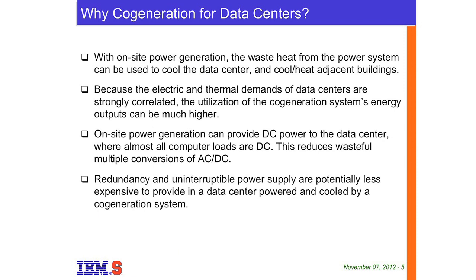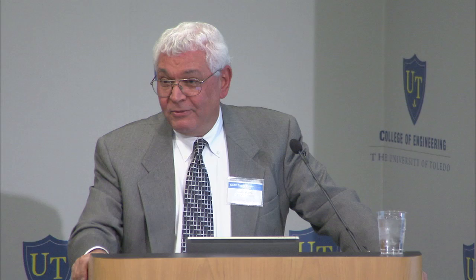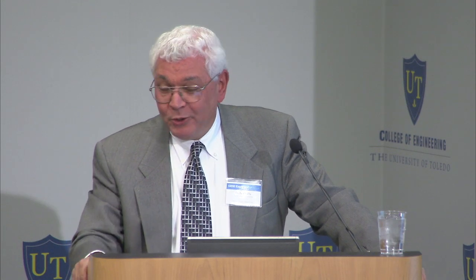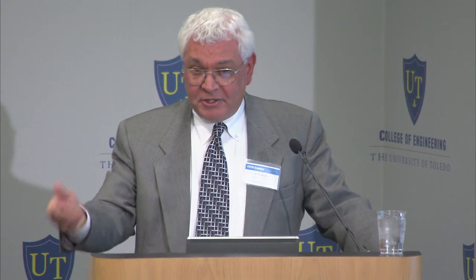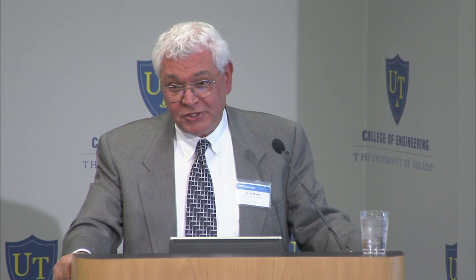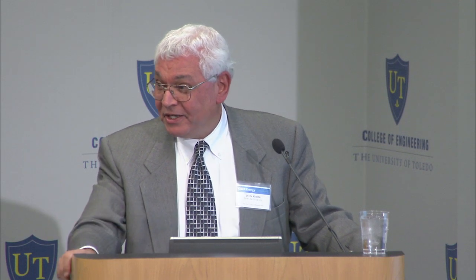The third advantage of using cogeneration in data centers is that computers are inherently DC devices, not AC devices. So what do we do in a data center? We take AC from the grid, rectify it, feed the batteries and the UPS, invert it again, distribute it, feed it into the computer where it's rectified again into high voltage DC, then step down to low voltage DC. That cascade of conversions—AC to DC to AC to DC—in a data center from five or six years ago would lose 25-30% of the electricity in that process.